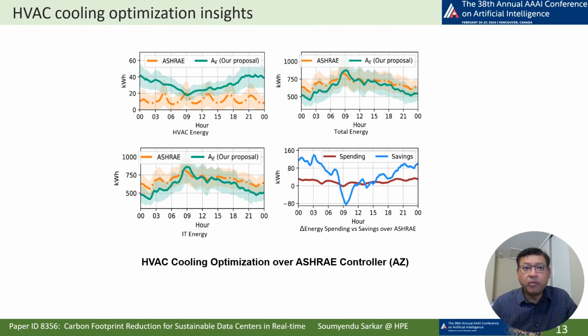Now the HVAC cooling: it can be seen that our approach, shown in green, spends more energy on cooling than the industry standard ASHRAE, shown in orange, on the top left. But there is significant saving on IT energy, as shown on the bottom left, which leads to a lowering of the total energy, shown on the top right.